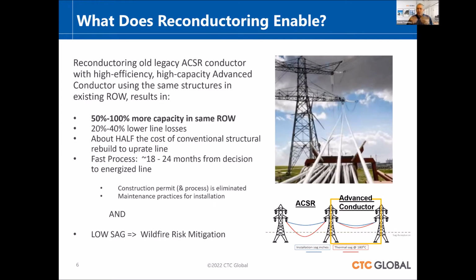So if you do reconductor, what do you get? Exchanging that wire, or in this picture, a group of wires, with high efficiency, high capacity advanced conductors using that same structure, you can get 50 to 100% more capacity now down that same right of way, depending on which technology you use and how the utility rates that right of way. As soon as you energize the line, though, you get a 20 to 40% lower line loss than the conductor that was on the structure previously.